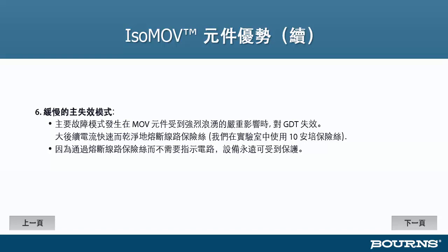Another unique feature of the IsoMOV protector is the primary failure mode, which is quite benevolent when the circuit is fused properly. It's very quiet, it's very simple, and because so little energy is involved, very little smoke is released. In our lab testing, there is no arcing or sparking. All that we see is that it blows the line fuse. We use a 10 amp fuse in our lab, and when you finally beat up the IsoMOV device to where the MOV just really isn't much of an MOV anymore, it still isn't leaky because the GDT is there.